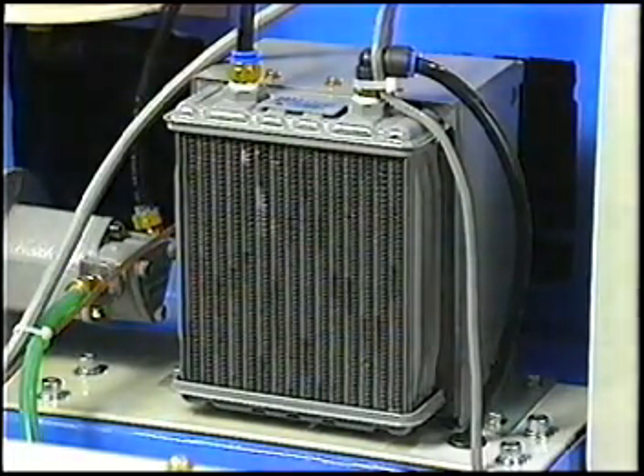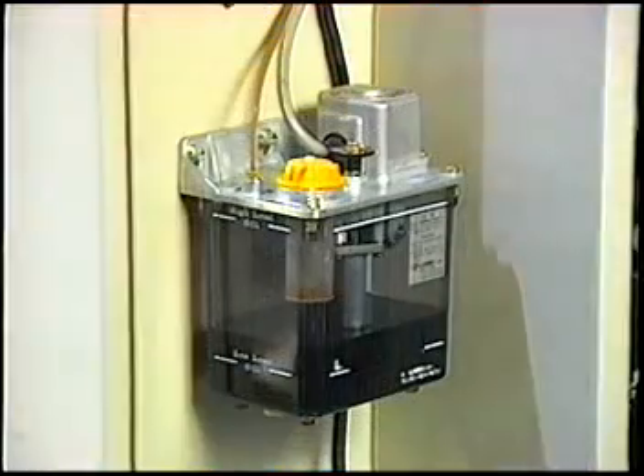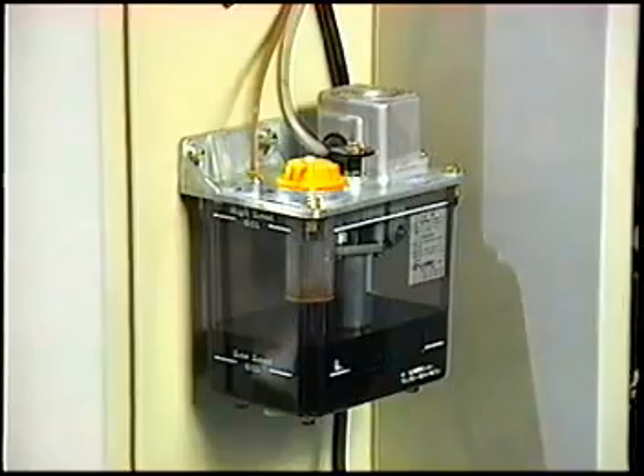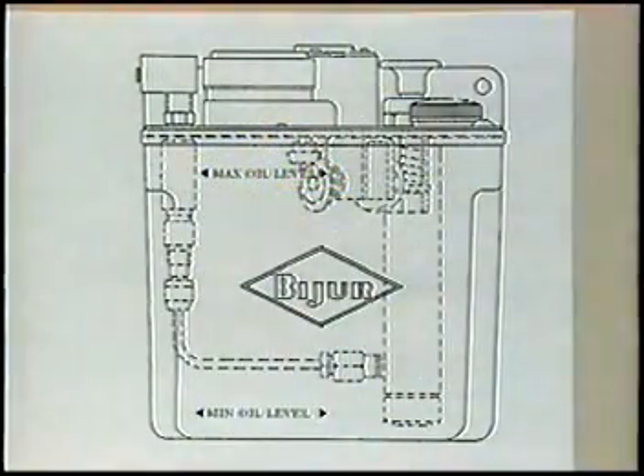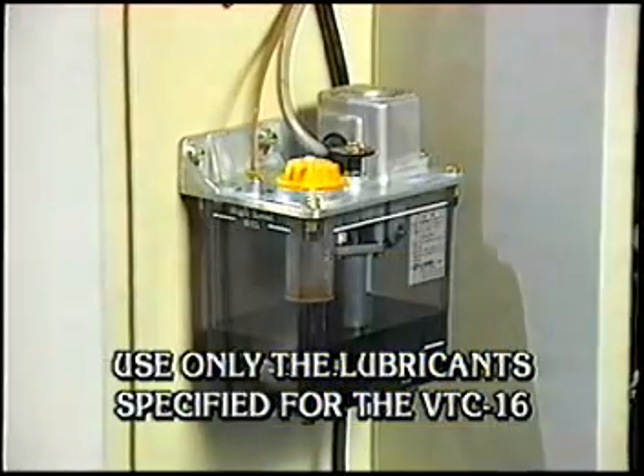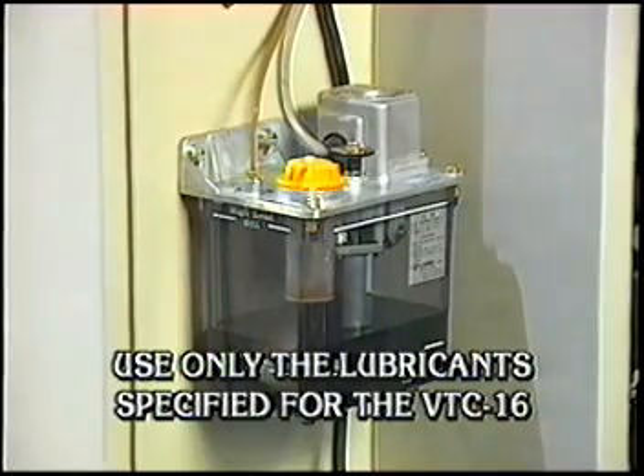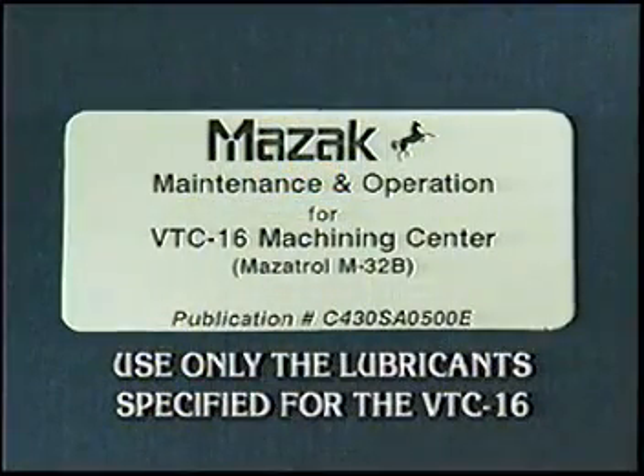compressed air. To the left of the column is the lubrication unit, which supplies oil to the X, Y, and Z axes. It is serviced by first draining the unit, then cleaning the filter located on the bottom of the pump unit and refilling with fresh lubricant. Use only the lubricant specified on the chart on the machine and also in the maintenance guide for the Vtc-16.